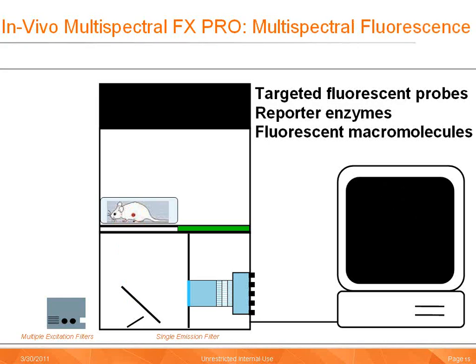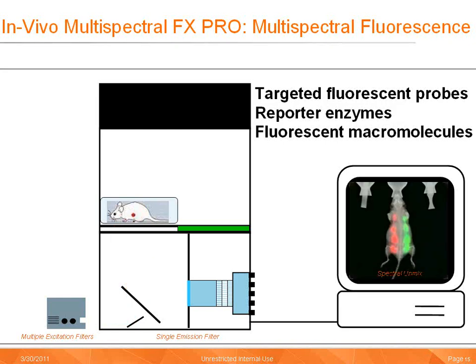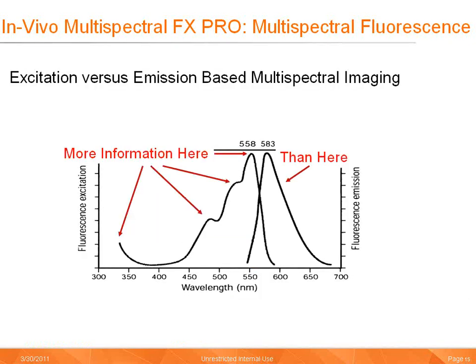Multispectral fluorescent acquisitions are achieved via sequential acquisitions at multiple excitation wavelengths. The images are collected and the spectral profiles are modeled and applied. It is possible to achieve spectral profiling using either multiple excitation filters or multiple emission filters. However, the CareStream multispectral systems are designed for excitation profiling. The rationale is that most fluorescent probes used in biological applications have inherently more distinct excitation profiles.